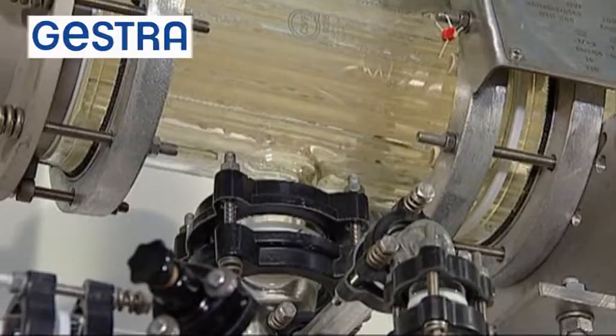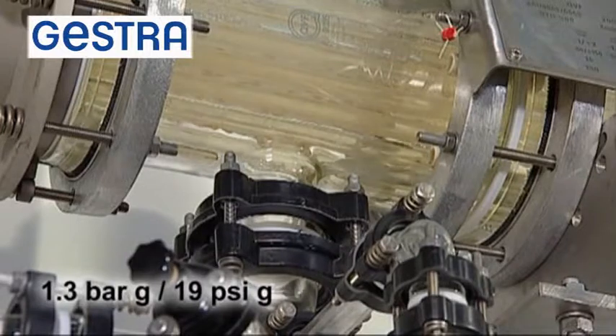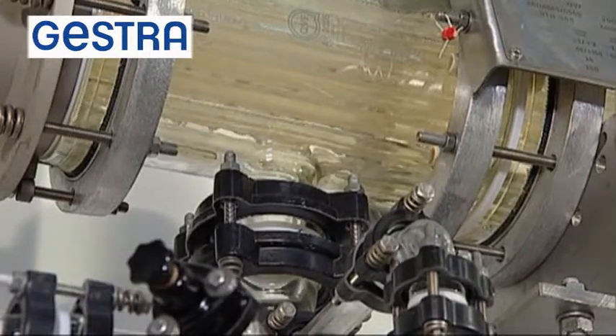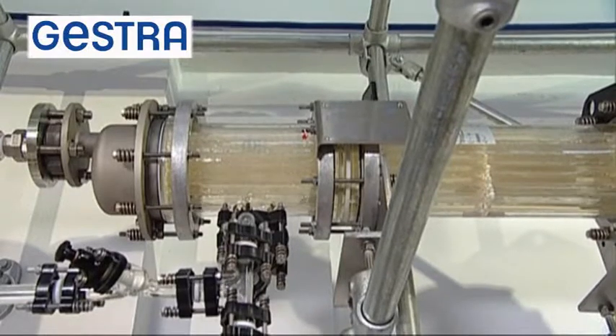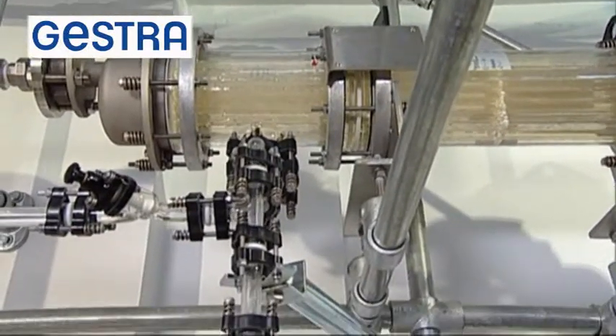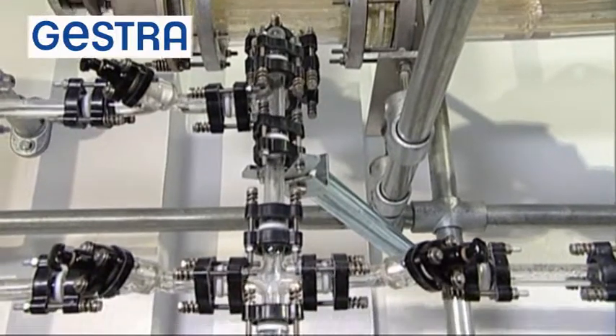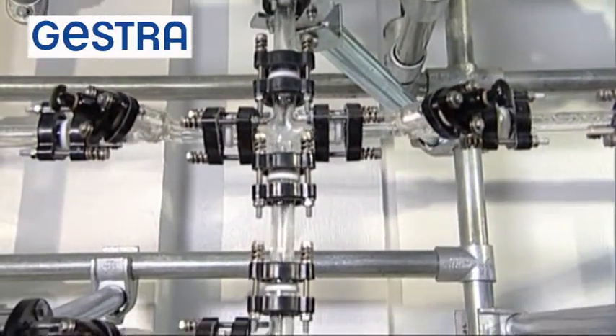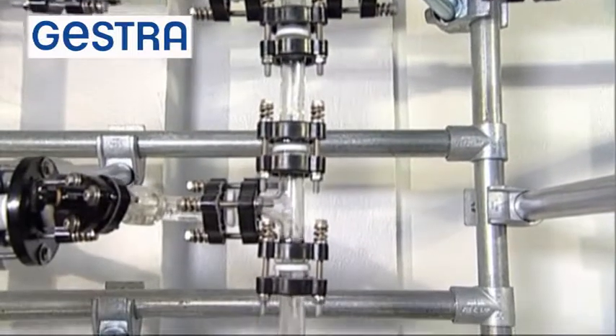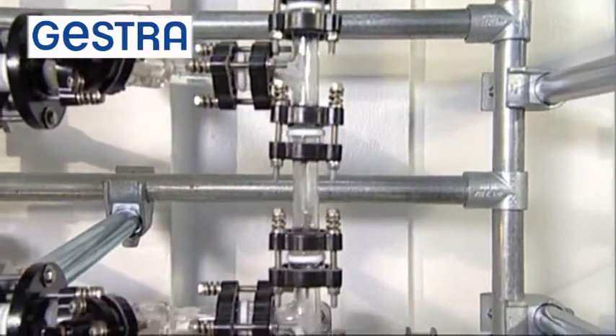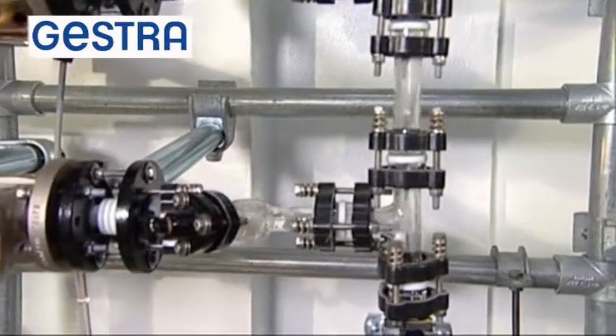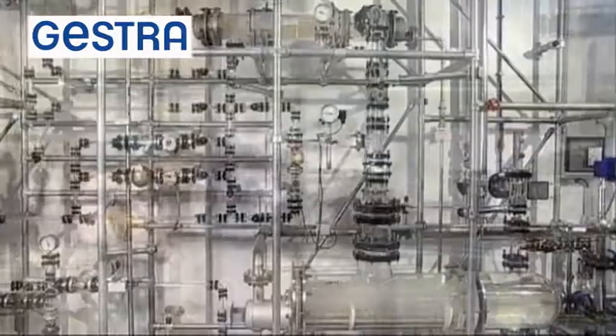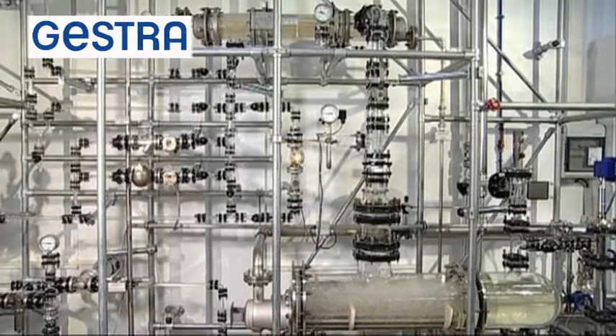When the operating pressure is increased again to 1.3 bar G, the float trap drains the heat exchanger immediately without banking up. It's absolutely essential to ensure drainage without any banking up for horizontal heat exchangers. An accumulation of condensate in the heat exchanger leads to the dangerous water hammer effect, floods the heating surface, and reduces the heat transfer coefficient by a factor of about 4. As a result, it's no longer possible to guarantee that the product passing through the heat exchanger is adequately heated at all times. It's recommended that thermostatic steam traps not be used in the case of large heat exchangers controlled on the steam side. Thank you for watching.